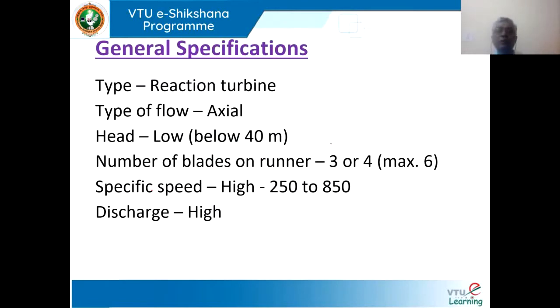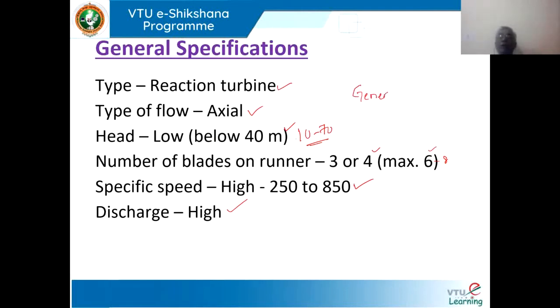In general specification, the working head is 10 to 70 meters, but below 40 meters it works most efficiently. It is an axial flow reaction turbine. Generally, the number of blades will be 4 to 8. Specific speed will be between 250 to 850. Discharge is high. When these conditions exist, we prefer the Kaplan turbine.